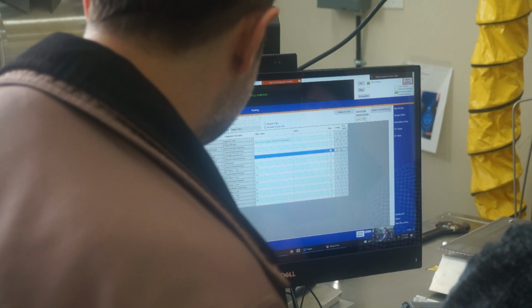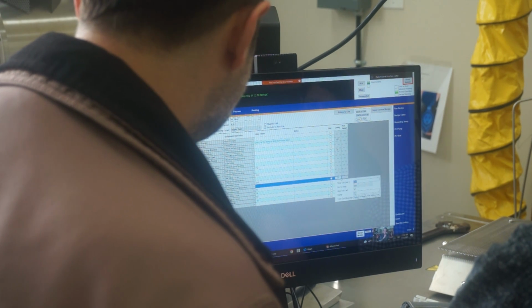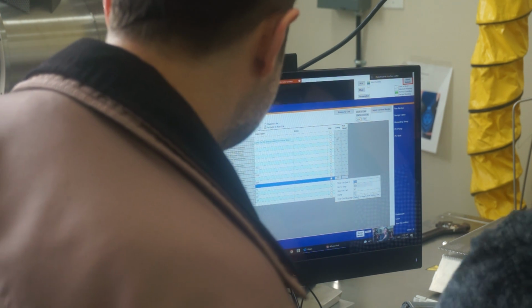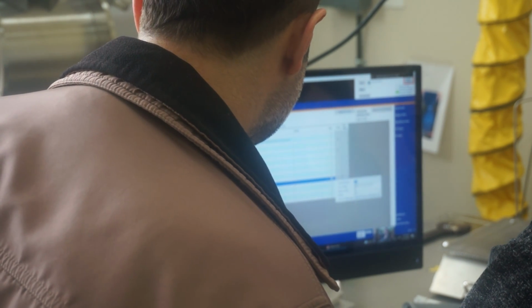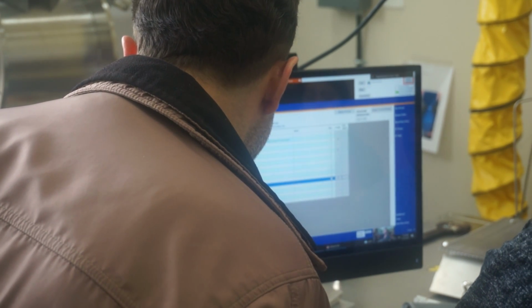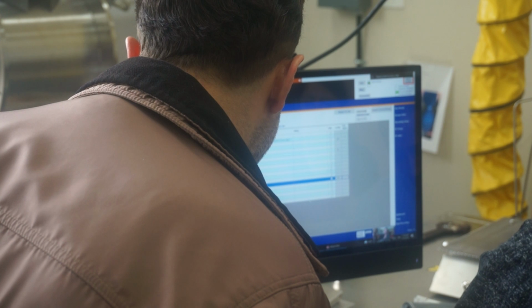Then it waits for up to 200 seconds for that vac switch to come off. If it goes over 200 seconds, like if you didn't have any more argon gas, it'll run the abort recipe. And then it'll say fail to reach atmosphere or ATM within set time. Then it sets the flow set point to 50, which dwells for 10 seconds, and at the end here, that's whenever you get that green bar.